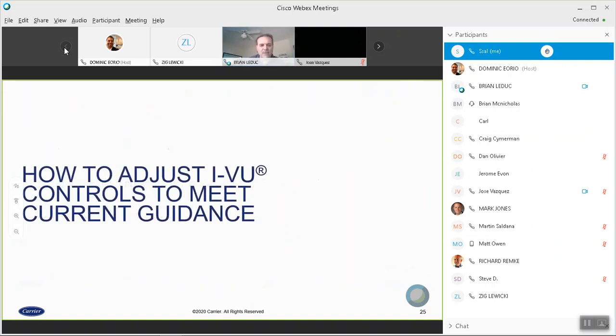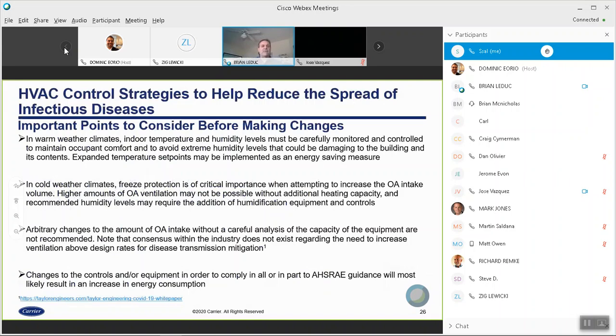Okay, how to adjust I-VU controls to meet the current guidance. Some things to think about before you make any changes. In warm weather climates, indoor temperature and humidity has to be carefully monitored and controlled to make sure you're still maintaining some degree of occupant comfort. You don't want to push set point changes to the point where the humidity levels could be damaging to the building or its contents.